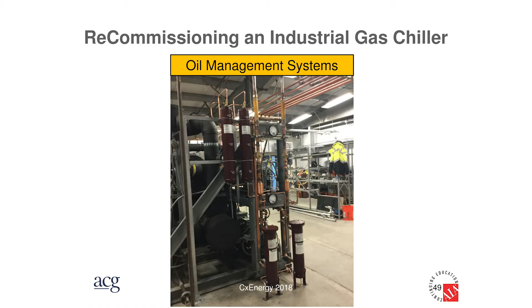The oil management system that we had to add, now I'm a mechanical engineer, so this was the coolest part for me. What was happening was that the oil would get pumped out with the refrigerant, and it wouldn't return adequately. At some flow rates it was okay, but as the machine was unloading and going up and down in its staging, sometimes that oil would get lost, the crankcase level would drop, you'd get a low-level alarm, and it'd shut down the compressor. And these are the problems that Melissa was saying that the operators had. They couldn't get it to work right, so after the first season, they just gave up on it.